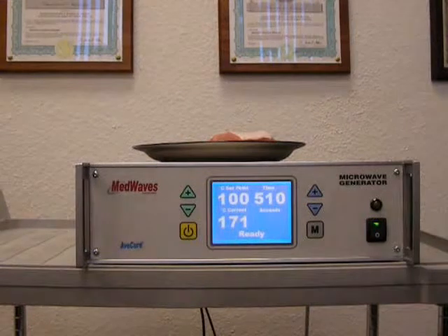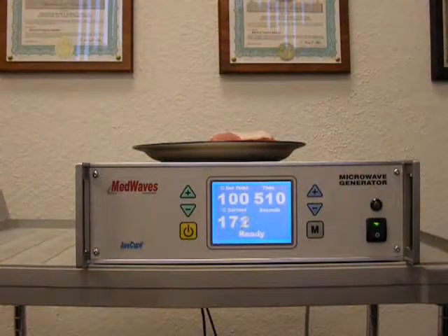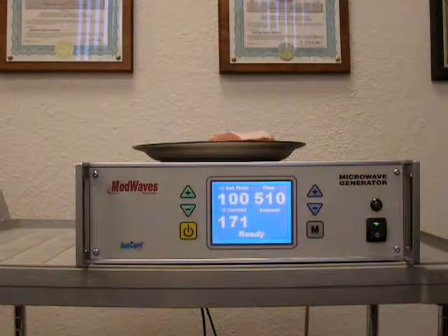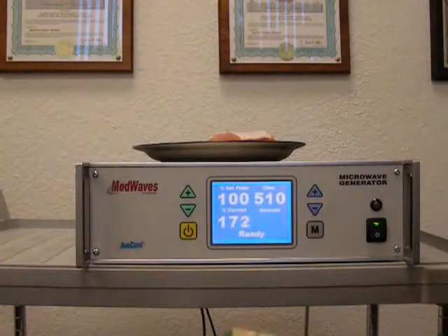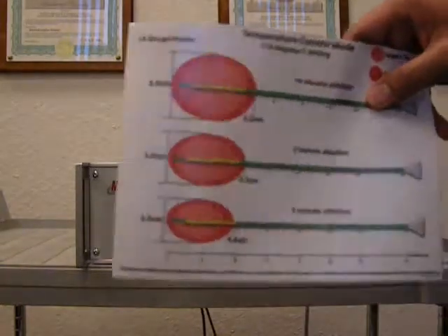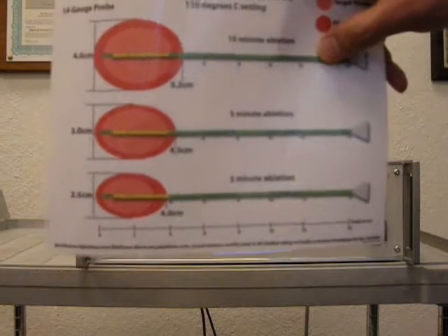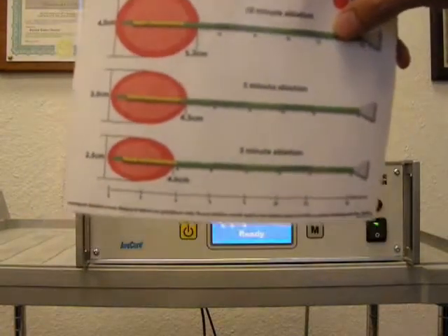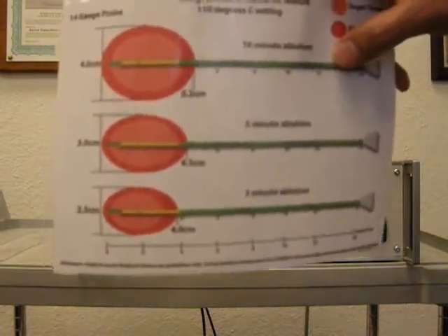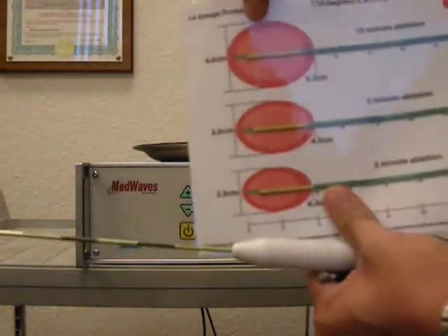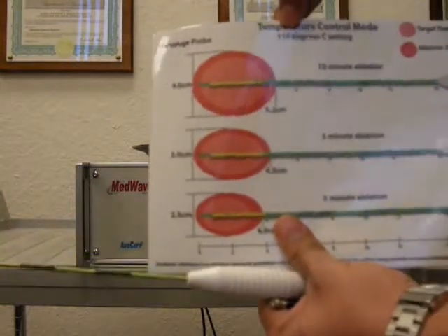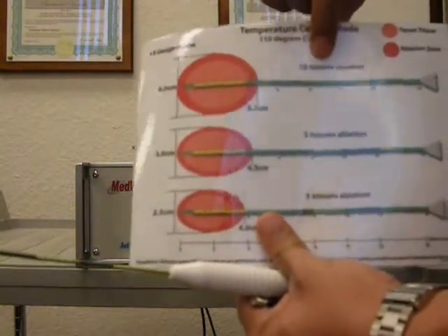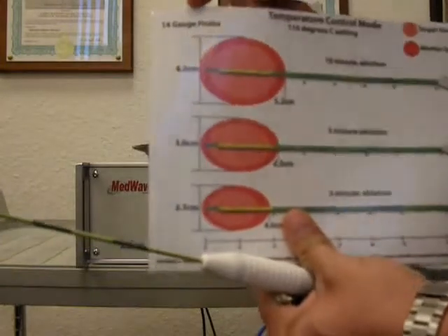Here's an example of a temperature control mode ablation using the microwave system. Here's a guideline that is given to the doctors as a reference for what types of ablation zones to expect. Let's say we want this size zone. Here we want a setting of 110 degrees centigrade at 10-minute ablation using the 14-gauge probe.